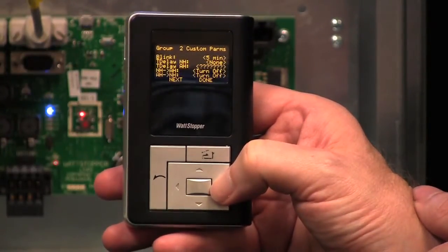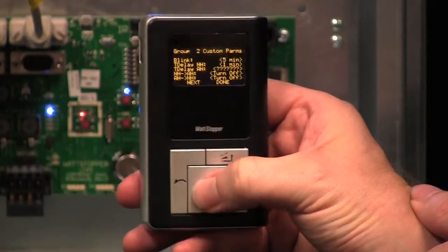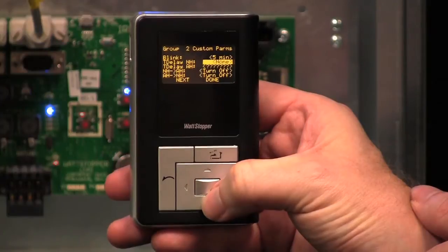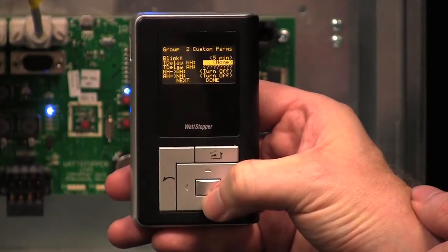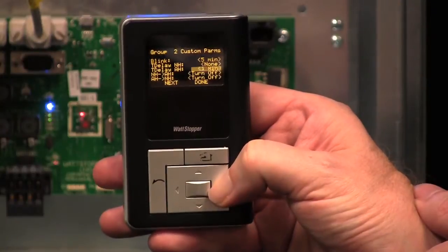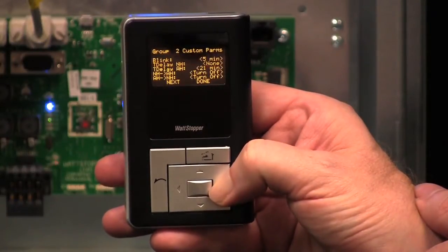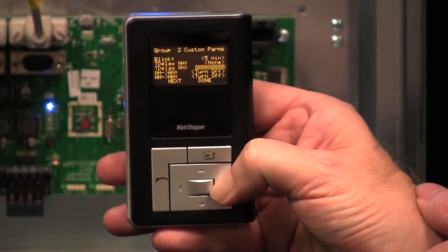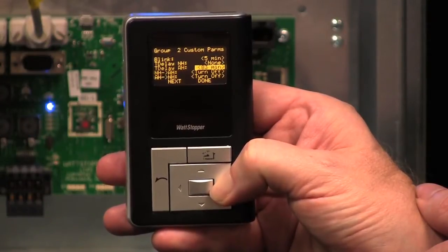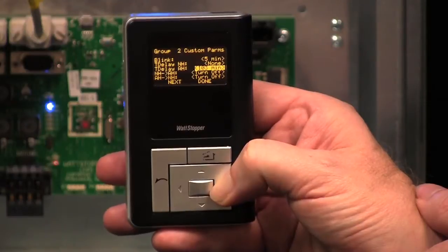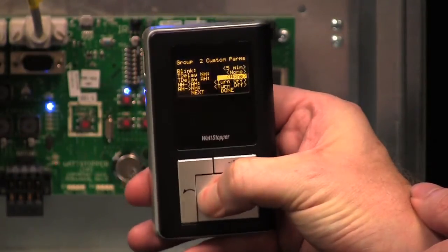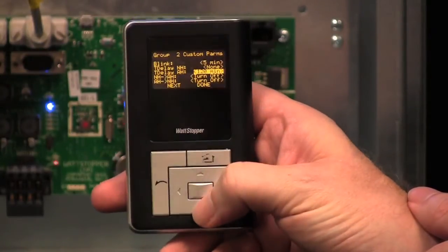The delay normal hours, for most buildings, if you think about it, during normal hours, you don't want lights to turn off automatically. So we're going to leave that one set as no. The next one, for after hours, though, we want to have a nice long time delay of, let's call it, 120 minutes. So this will give anybody who overrides the lights a 2-hour time delay whenever they override the lights. Let's go up to 120. I could have obviously gone around the bend.